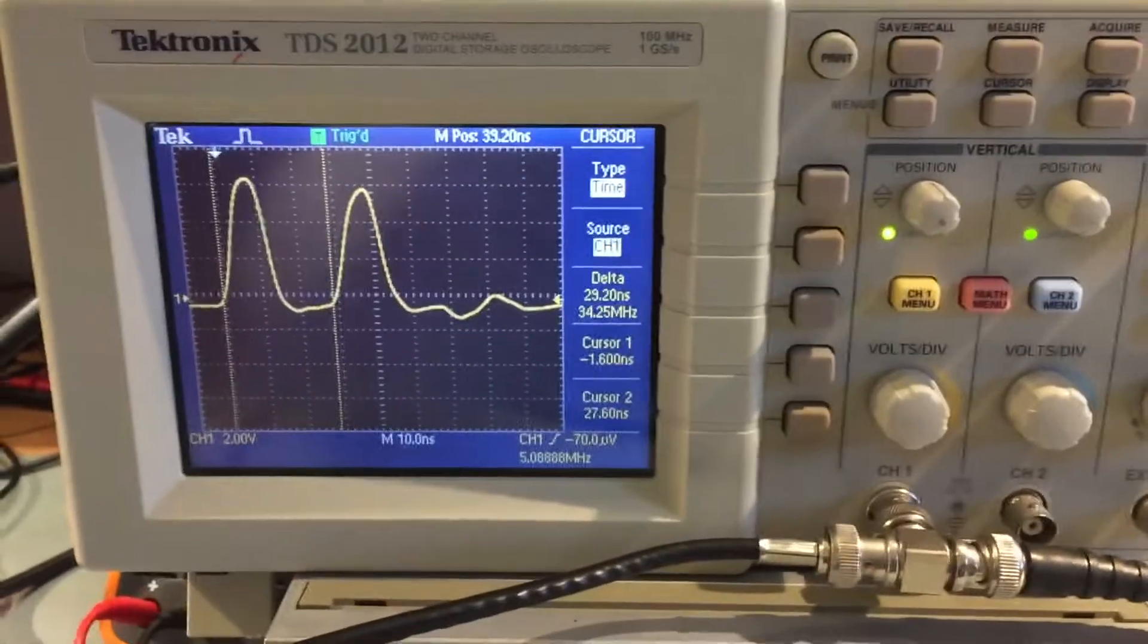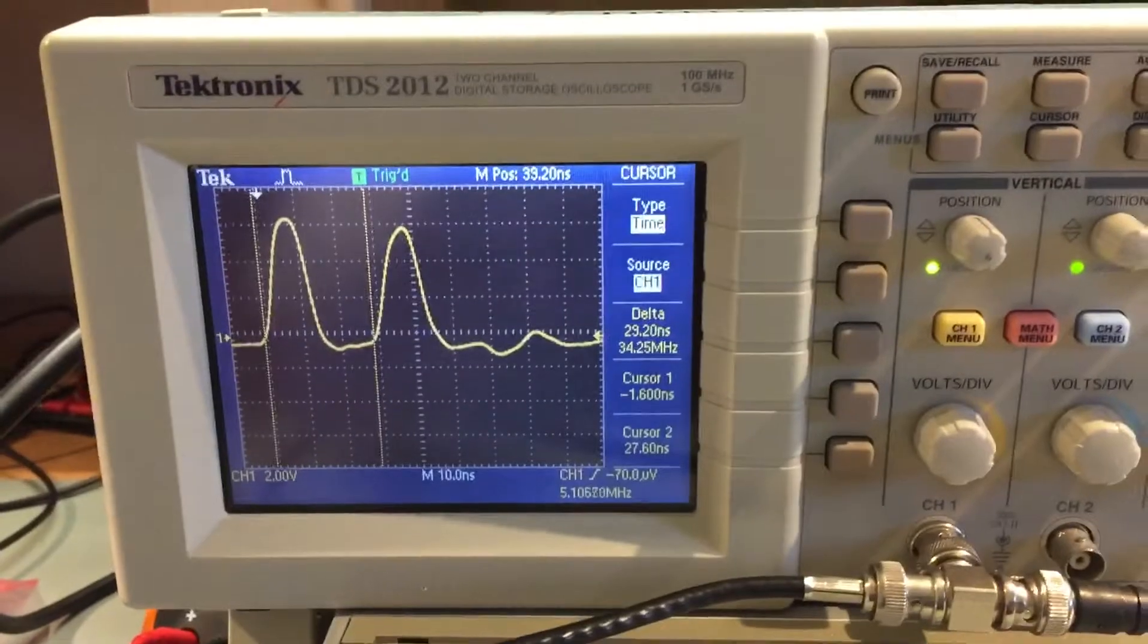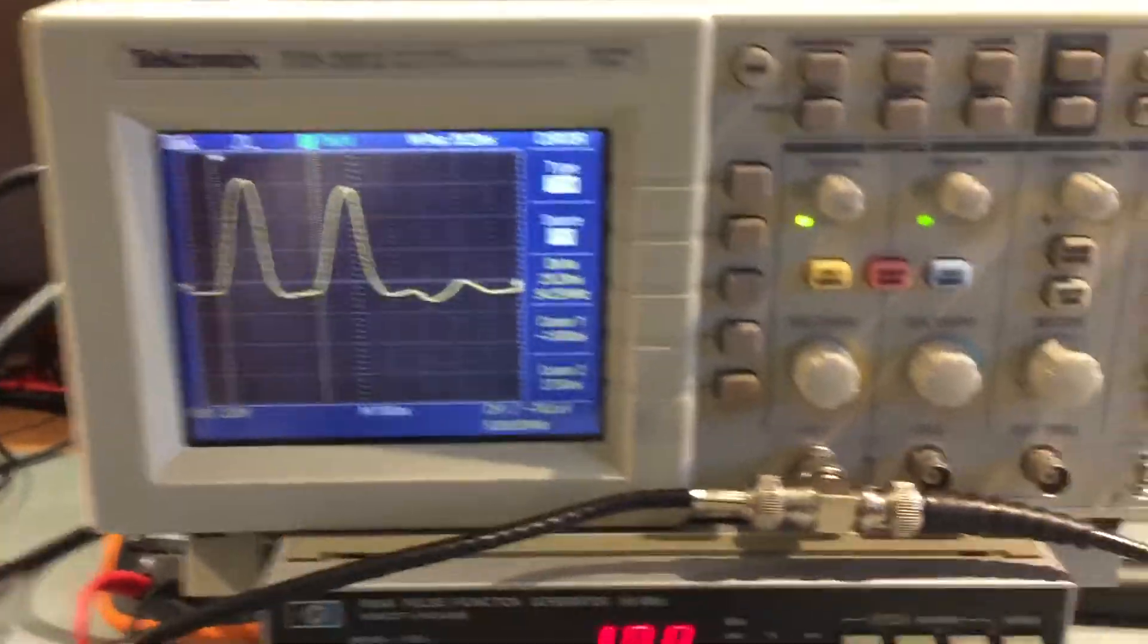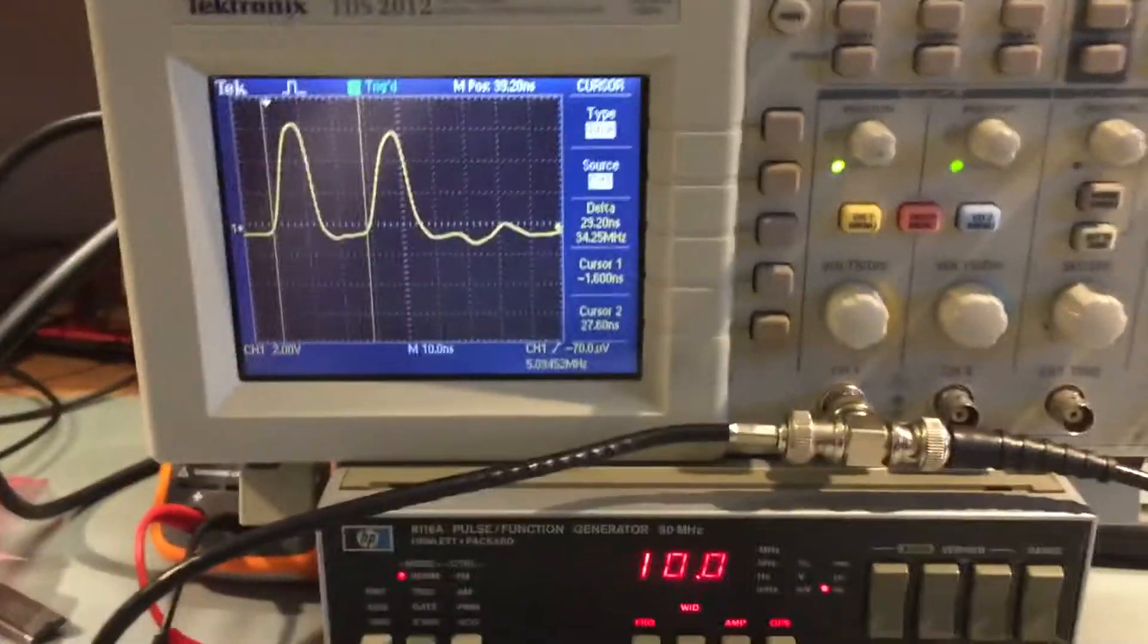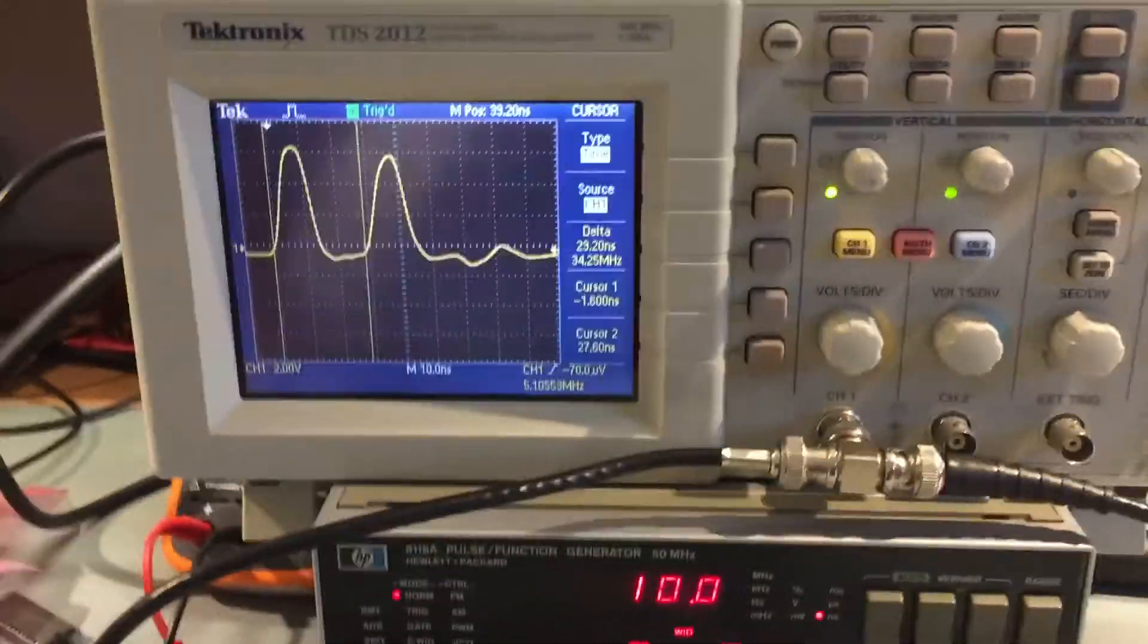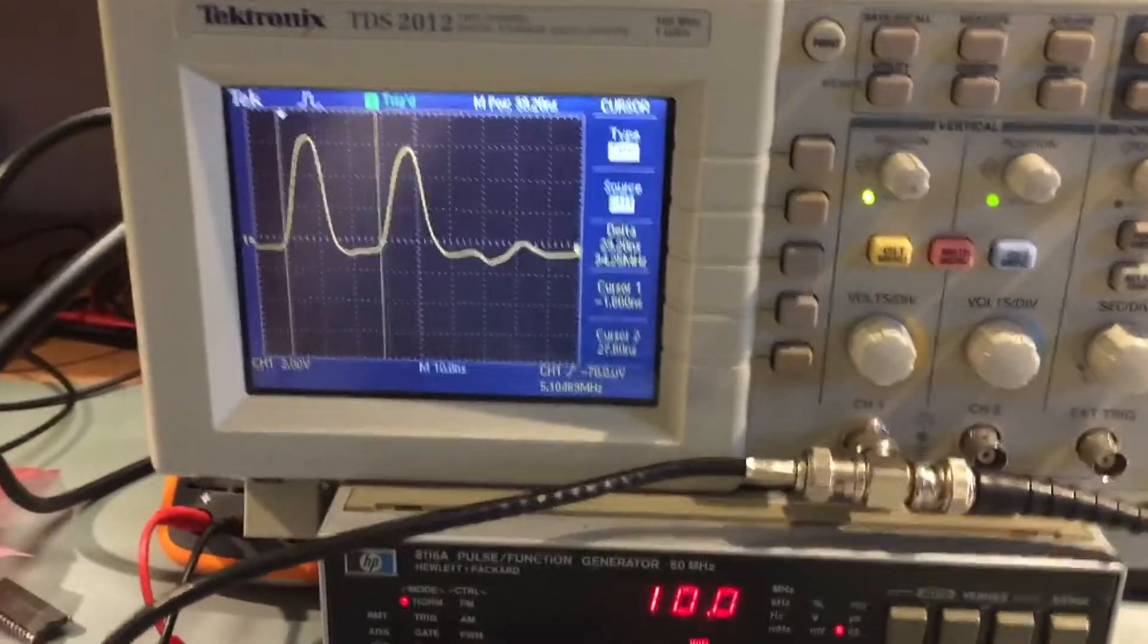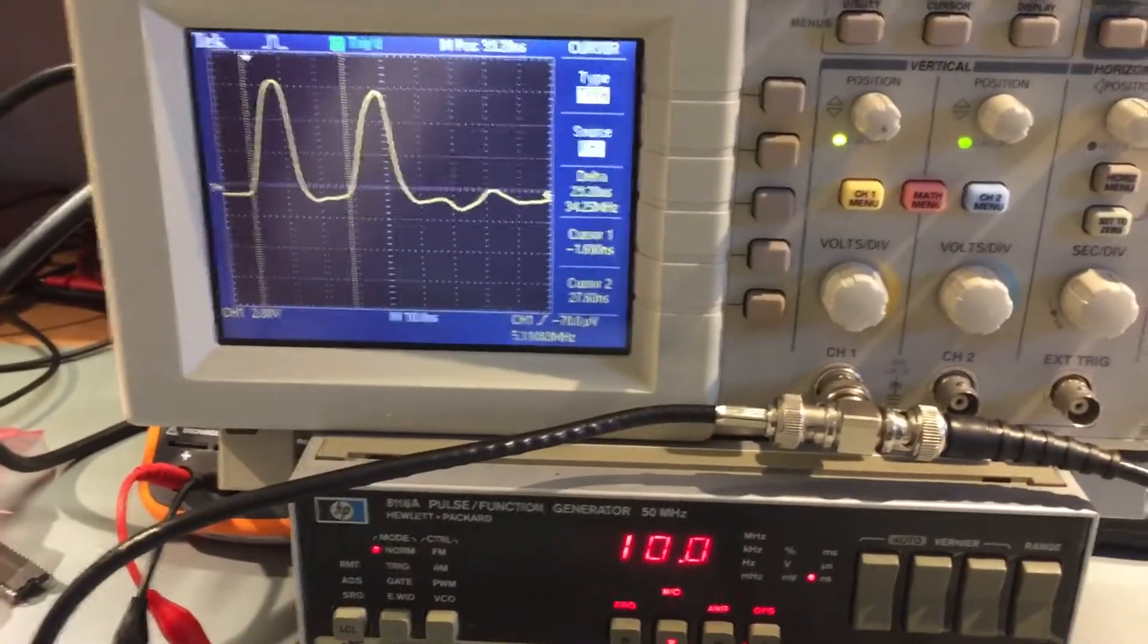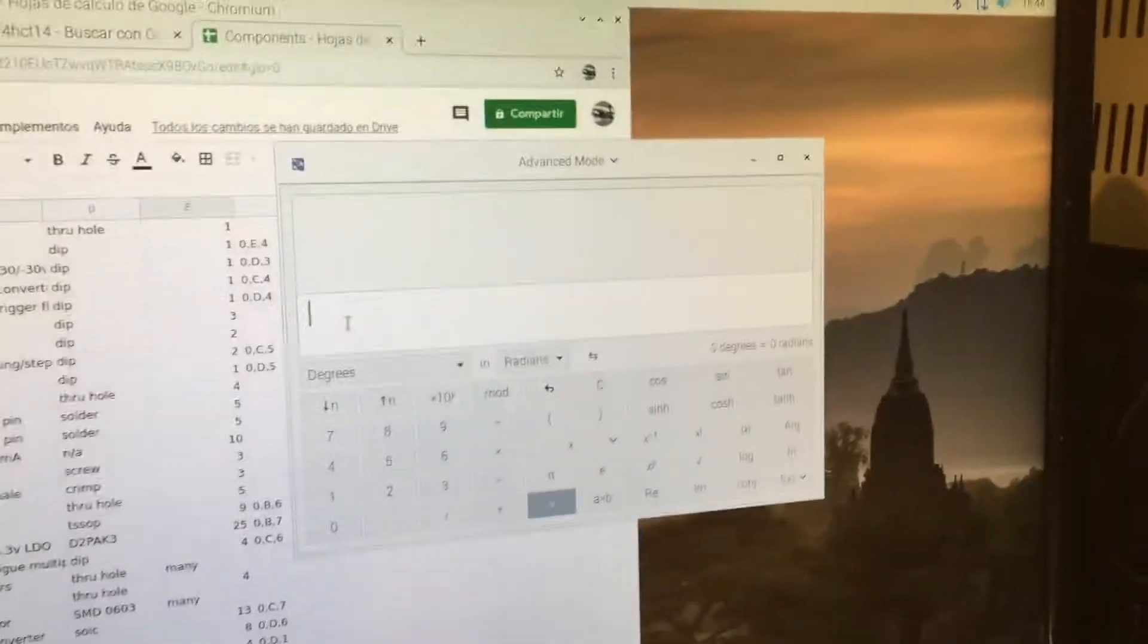Now, light travels at basically 0.3 meters per nanosecond. And in RG58, there's a velocity factor of about 0.66. So, if we get our calculator here.